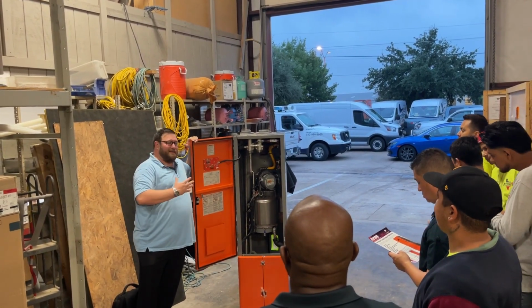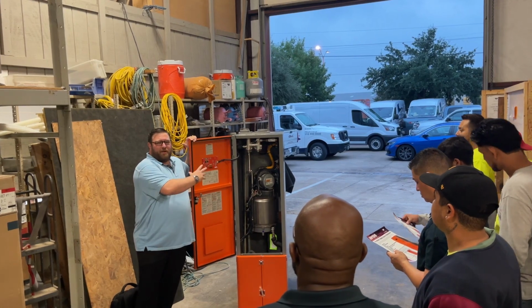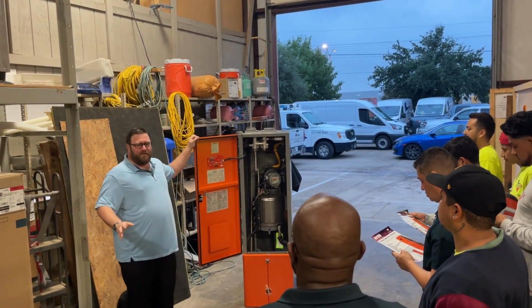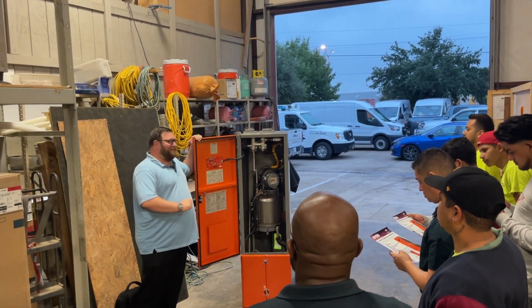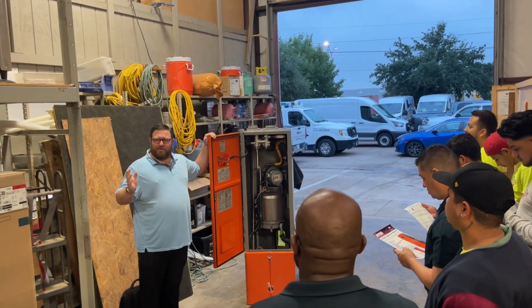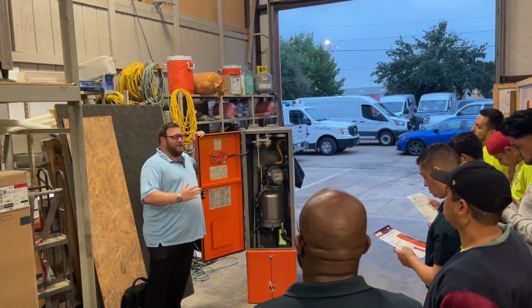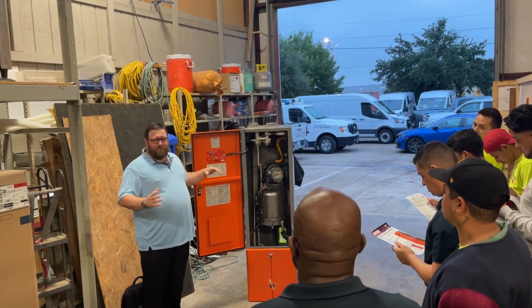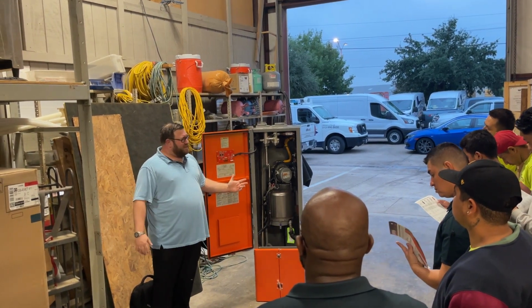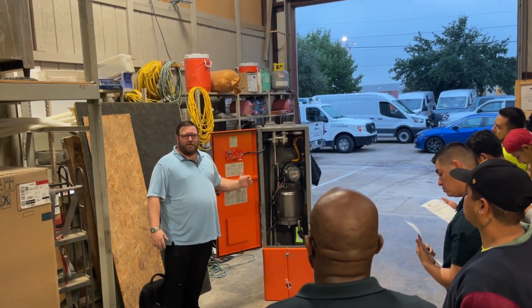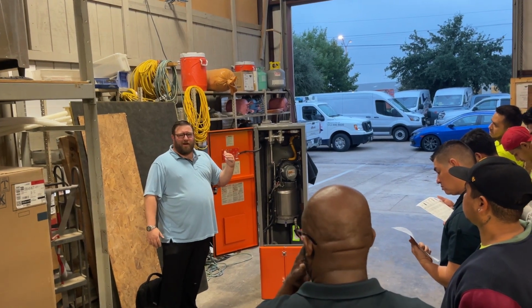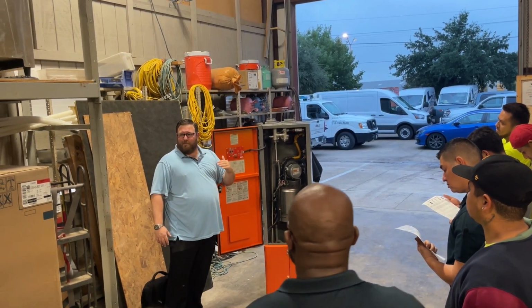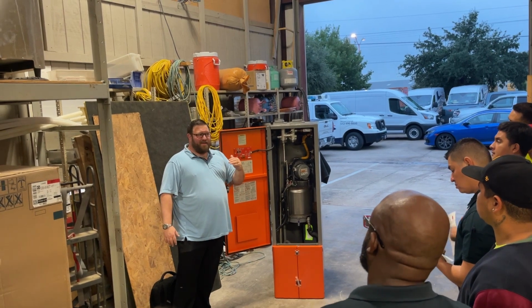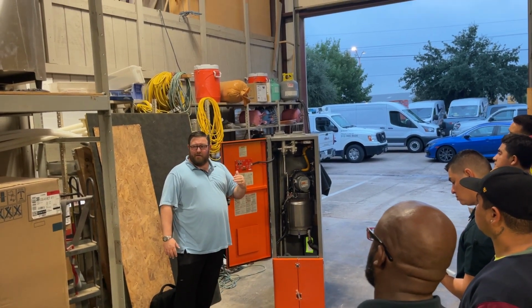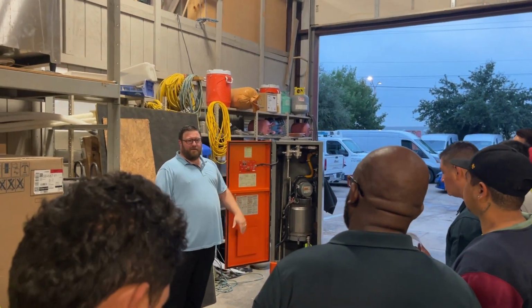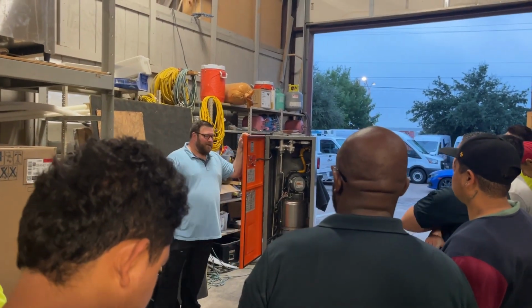Let's say this is sized correctly, you put it in, everything's perfect. Most of the time everything's great, but every once in a while they turn everything on out of the norm and it's just more than it can handle. Instead of reducing flow across all fixtures, if you set 140 degrees, it'll drop down to 135, 130, whatever it can handle at that moment. But at the end of that, it's still ready with hot water. You're not waiting for recovery. So the way we see it, that's a much better place to be in.